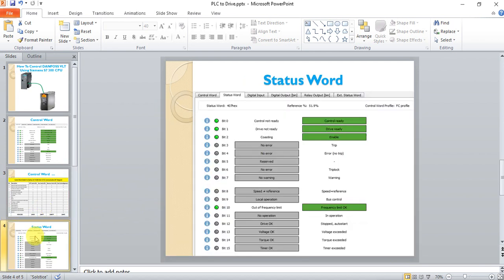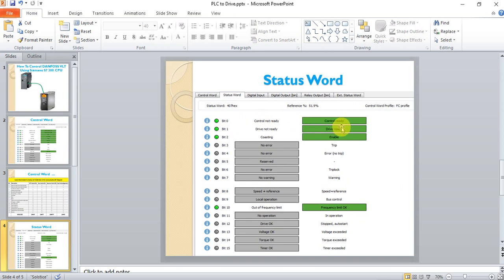The other important parameter is the status word. The status word tells us the current status of the drive and gives information to the PLC. It also has 16 bits or one word. For bit 0: if it is 0 it means controller not ready. Likewise, if bit 3 is 0 it means no error; if bit 3 is 1 it means tripped.